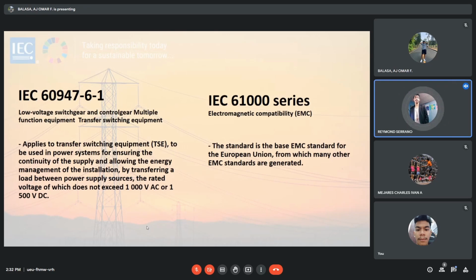So, next is IEC 60947 Part 6-1. Low voltage switchgear and control gear, multiple function equipment, transfer switching equipment. It applies to transfer switching equipment (TSE) to be used in power systems for ensuring the continuity of the supply and allowing the energy management of the installations by transferring a load between power supply sources. The rated voltage does not exceed 1000 volts AC or 1500 volts DC.